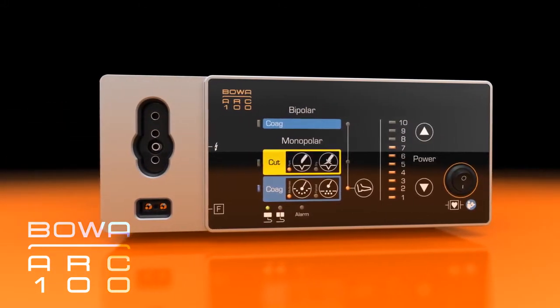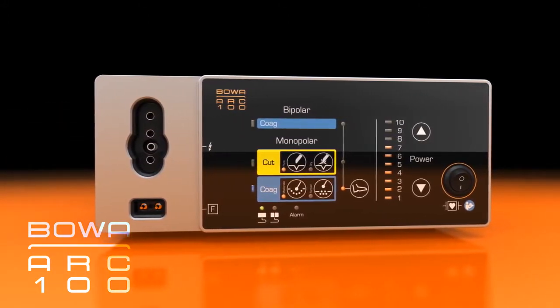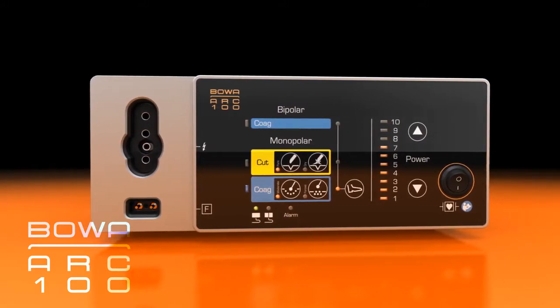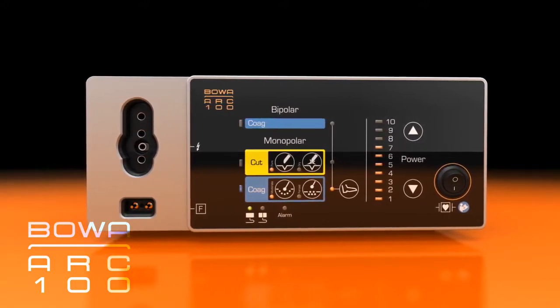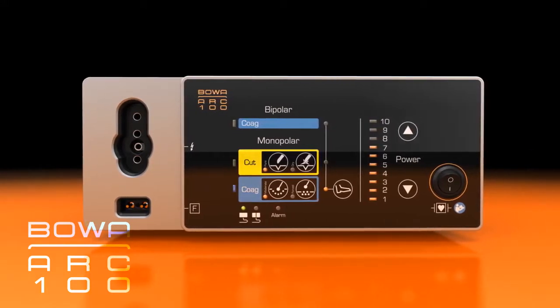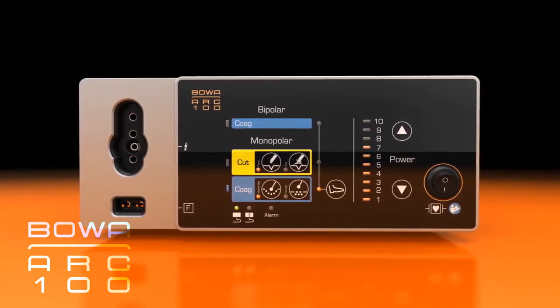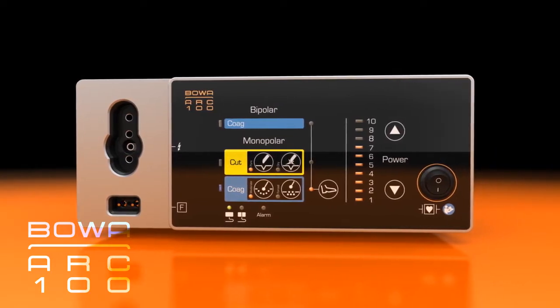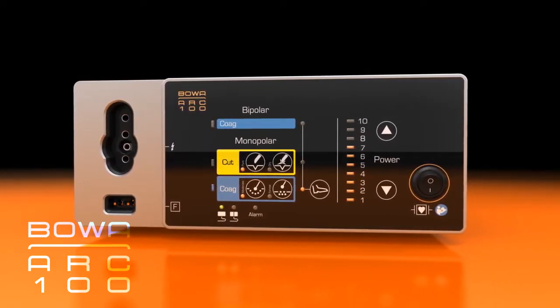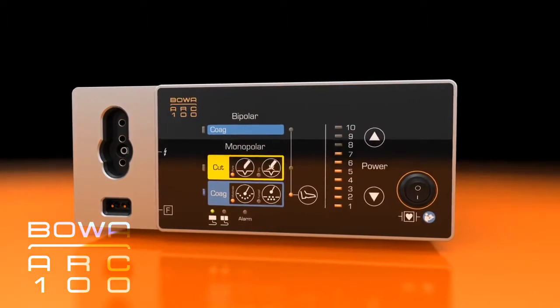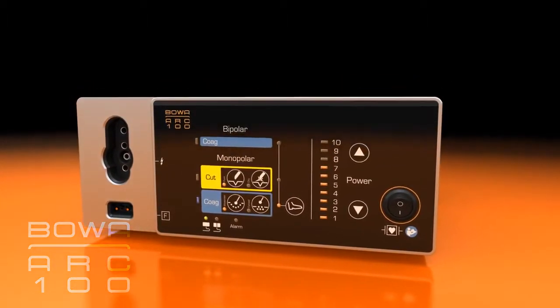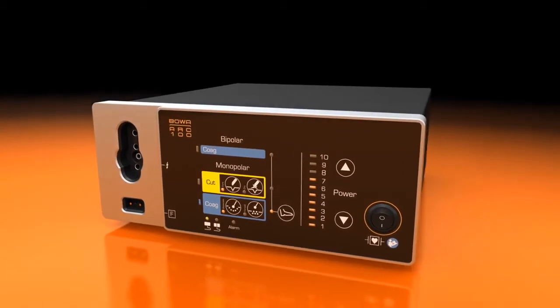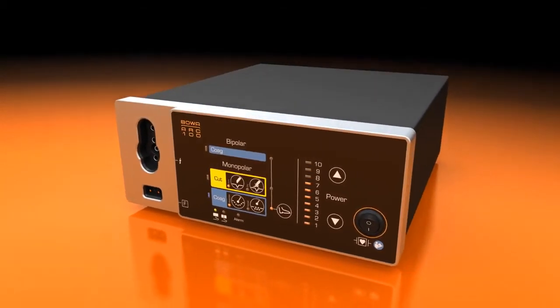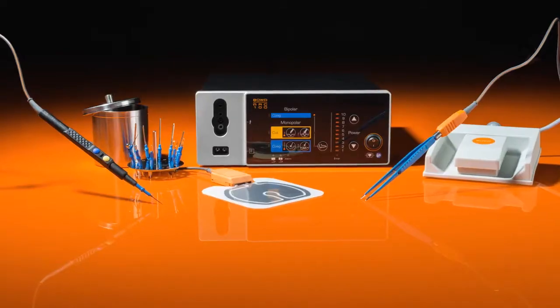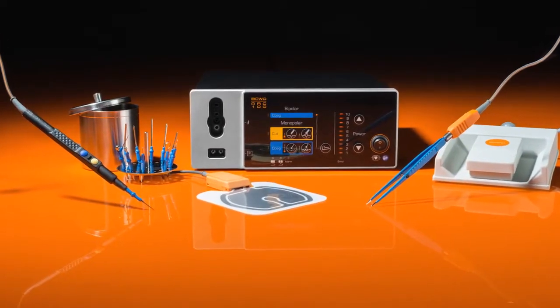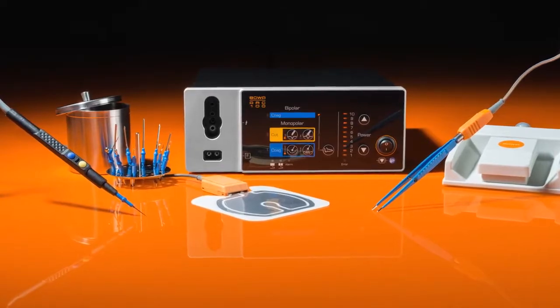Various monopolar and bipolar functions are available: standard cutting, dry cutting, moderate coagulation, forced coagulation and bipolar coagulation. Operation is self-explanatory. All functions and power settings are visible at all times and can be selected by tapping with a finger. Easy neutral electrode monitoring provides high-level patient safety. This guarantees safe working to a high clinical standard. You'll be perfectly equipped with the extensive range of basic equipment for the ARC 100.